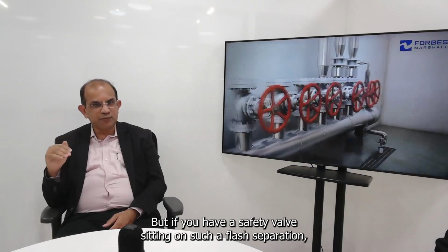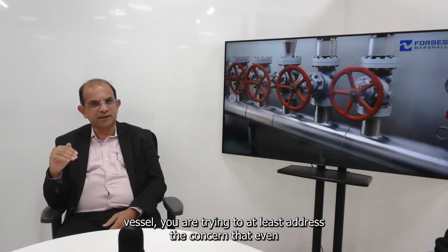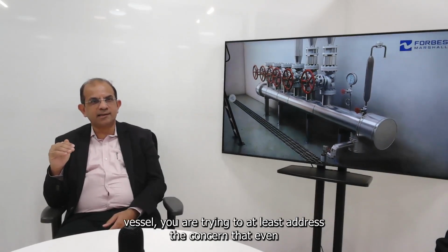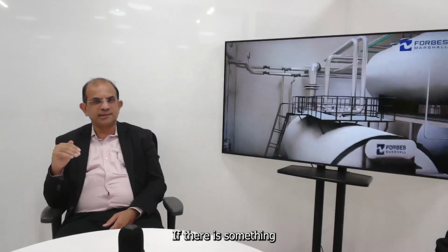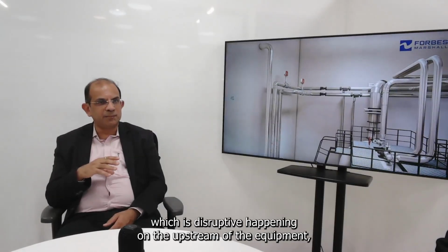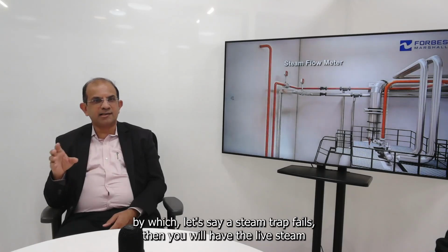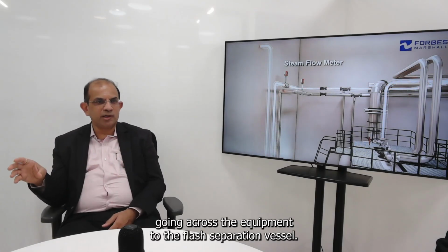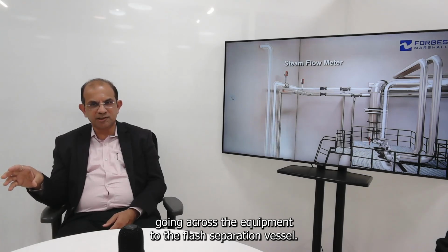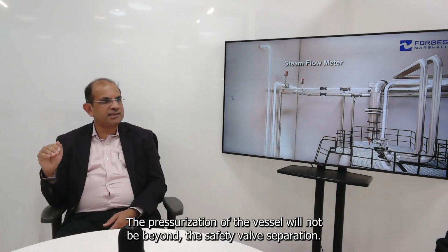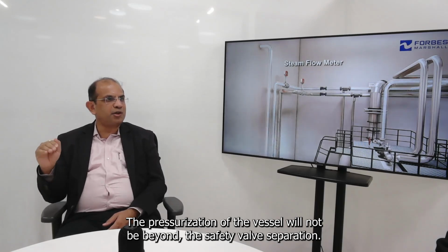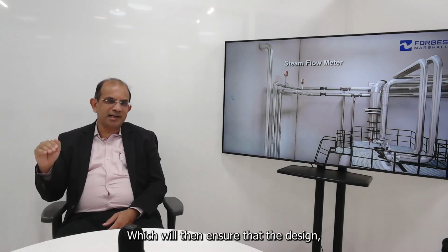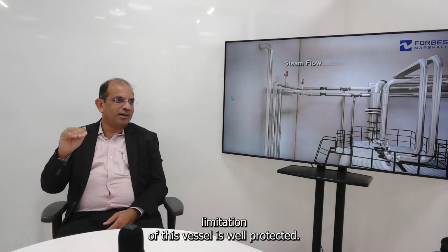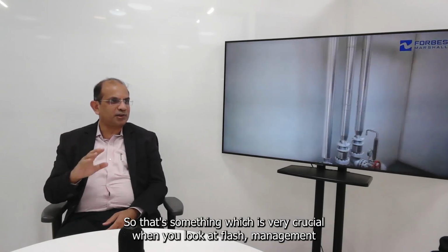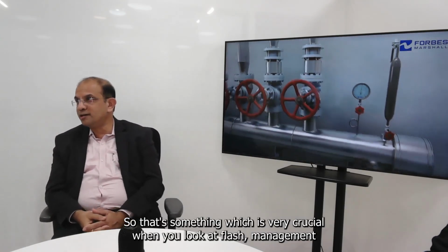But if you have a safety valve sitting on such a flash separation vessel, you are at least trying to address the concern that even if something disruptive happens upstream of the equipment, let's say a steam trap fails and live steam goes across the equipment to the flash separation vessel, the pressurization of the vessel will not be beyond the safety valve set pressure. Which will then ensure that the design limitation of this vessel is well protected. So that's something very crucial when you look at flash management on one hand and condensate recovery.